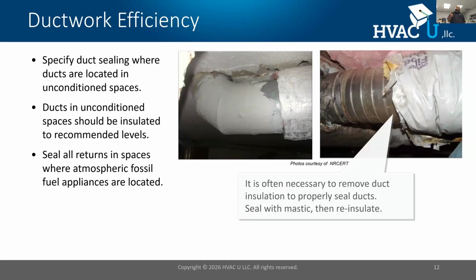So you need to design them first with ACCA Manual D, and then they need to be sealed. However, if you seal ducts that were not designed properly, you're going to make the problem worse as far as static pressure, like Brett mentioned earlier, and you're going to damage equipment. So ducts have to be sized, and then they have to be sealed in all cases. Now, what about ducts outside the thermal pressure boundary, outside our building envelope? How should we handle those? If those outside areas are vented to atmospheric pressure, such as a vented attic or crawl space, we need to not only size them appropriately and make sure they're sealed, but we also need to insulate them. They need to be insulated.